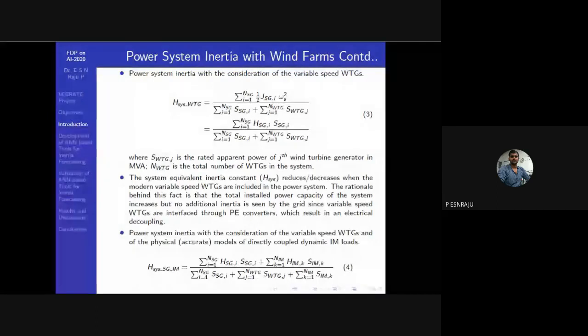At the same time, it will increase the total power capacity in the system, which leads to a reduction of inertia in the power system. When we consider dynamic accurate models of induction motors, we can also include the inertia contribution from the induction motors and their total capacity in equation 4, similar to previous expressions.